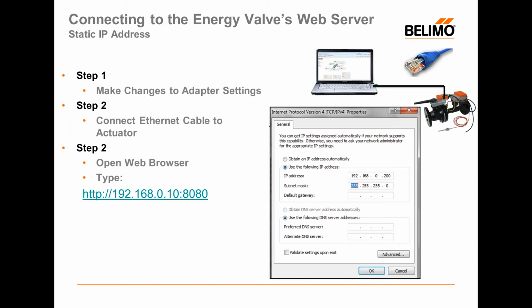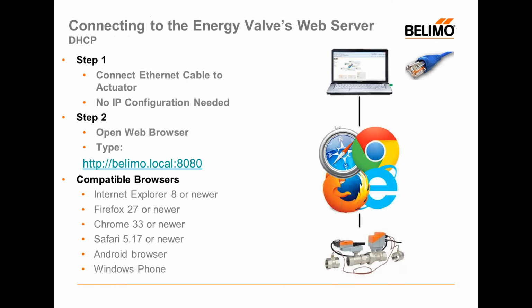Here you can see we have a static IP address set of 192.168.0.200 with a standard subnet of 255.255.255.0. Once you've set these addresses and the subnet in the settings, click OK. You'll have to restart your PC. Once your PC is rebooted, you can then use a standard Ethernet cable, connect the cable from your PC to the actuator's Ethernet port, open up a web browser and type in 192.168.0.10:8080, and it will bring you to our login screen.